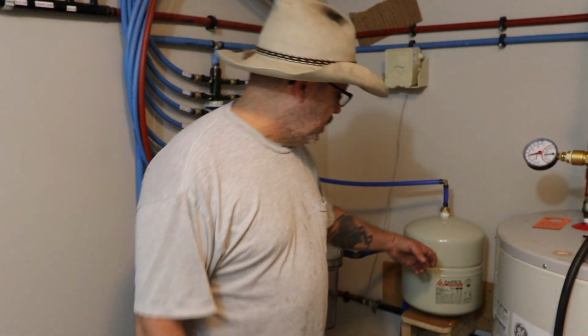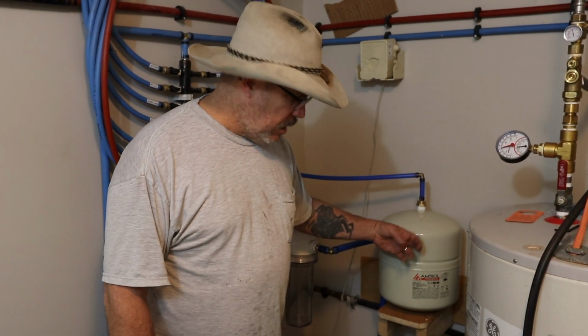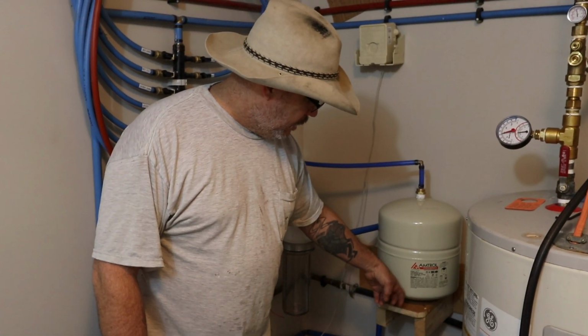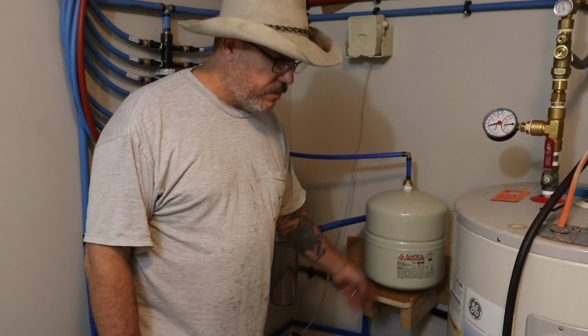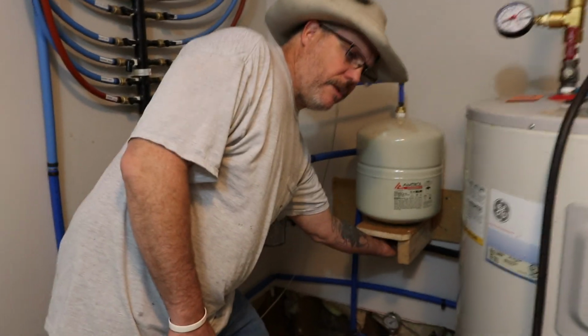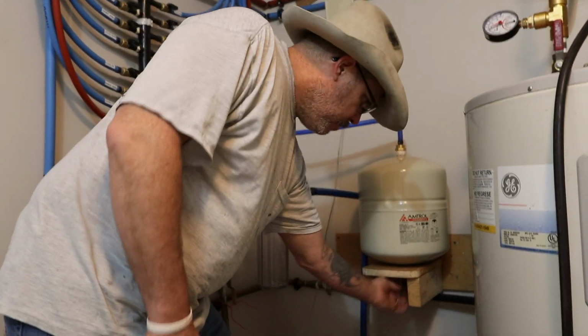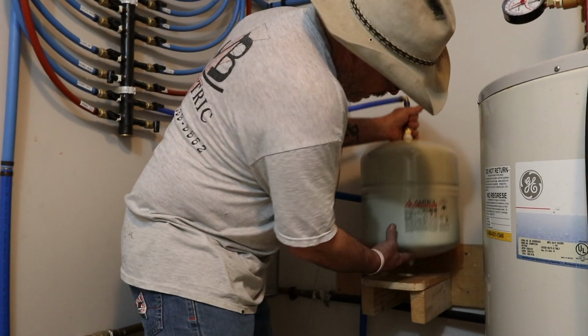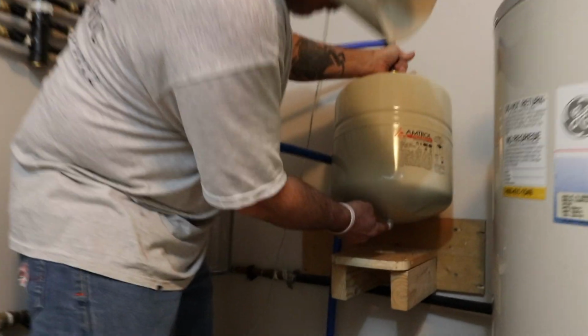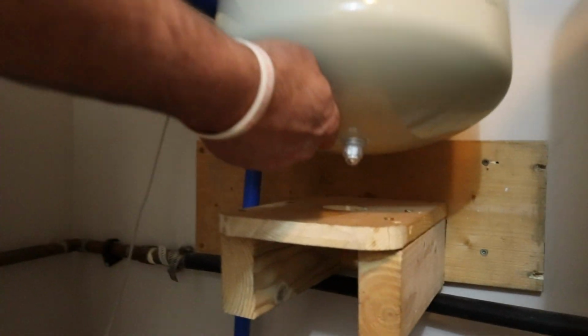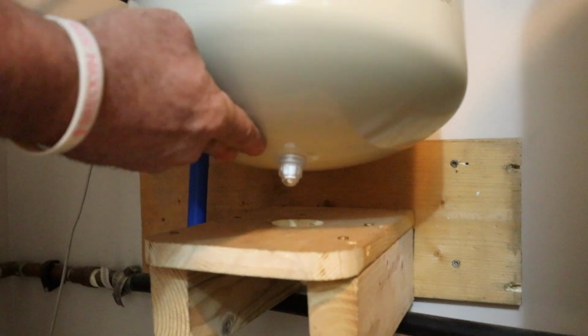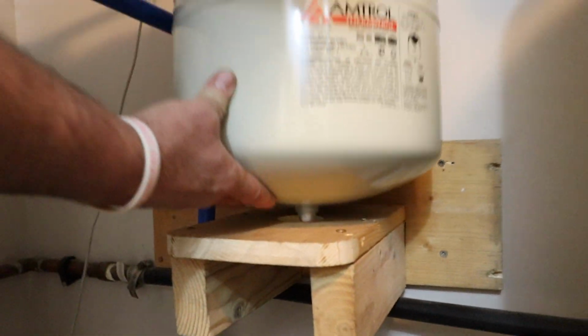You can tell if these tanks fail: it sounds hollow up here and solid there, and it's more hollow down here, so you can tell. Also, this tank has a little clear indicator on the bottom, and you can see it. If you lift it up, you can somewhat see if that thing failed, because it will change colors and tell you that you've got water where you're not supposed to.